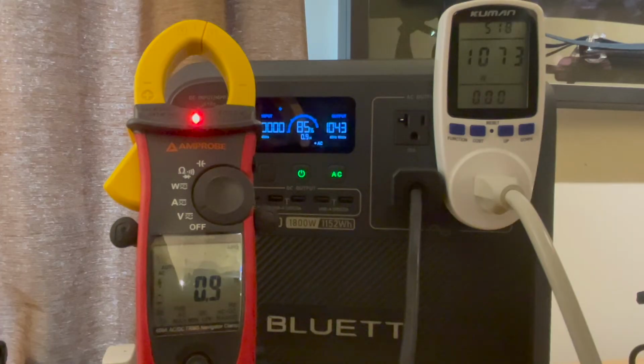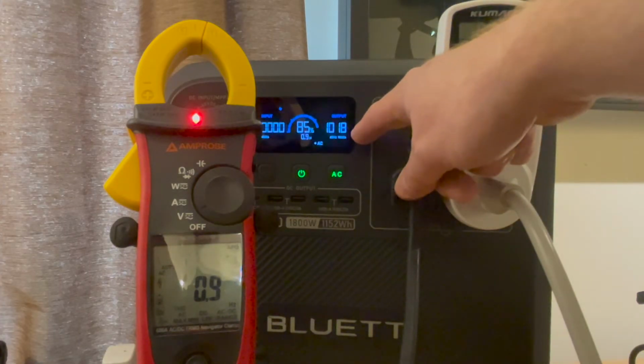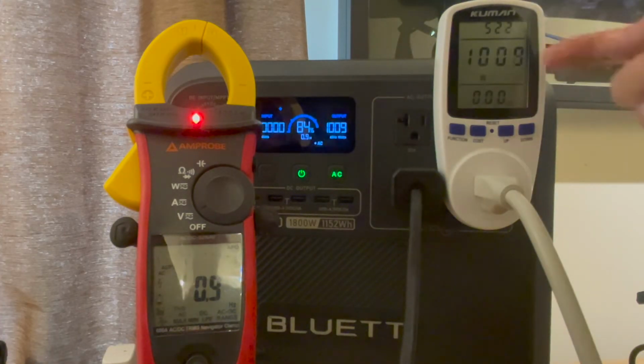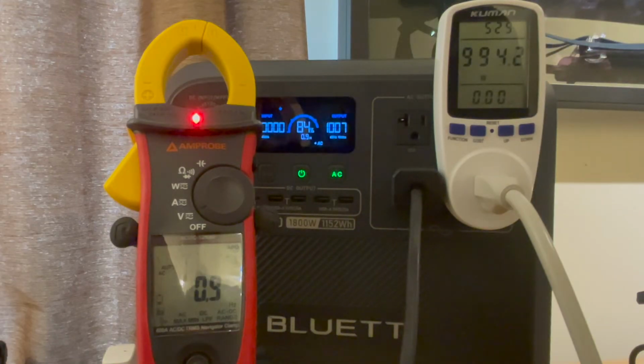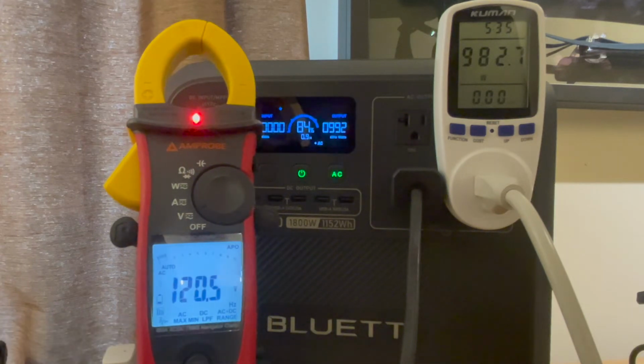And let's kick on some loads here. So we've got 1,000 watts of load going, this meter says 1,000 watts, so we're running at about 50% of the max load of the inverter right now. It's an 1,800 watt inverter, I'm at about 1,000 watts. And my harmonic distortion meter is at 0.9%. Very nice, that's actually really, really impressive that it can do that.